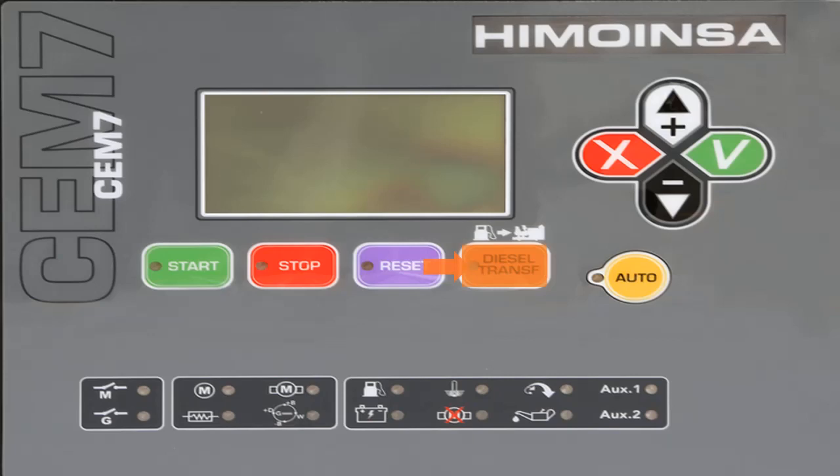In automatic mode, the system manages the fuel transfer pump by monitoring the minimum and maximum activation thresholds. In combined mode, the fuel transfer pump is managed according to automatic mode, but also allows activation by pressing the diesel transfer button. Manual activation is limited by the maximum deactivation threshold pre-programmed in the controller.